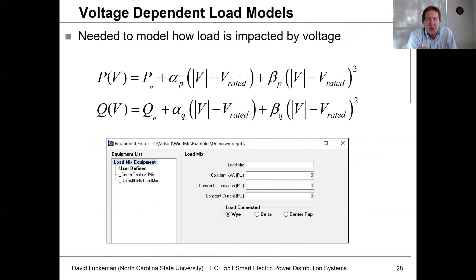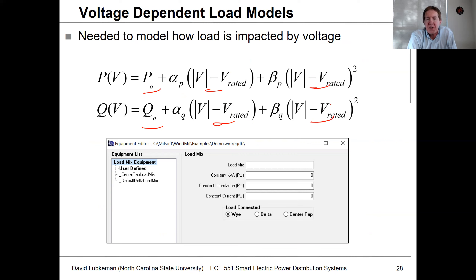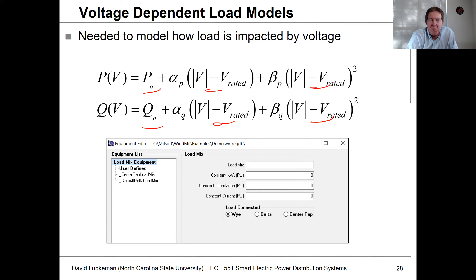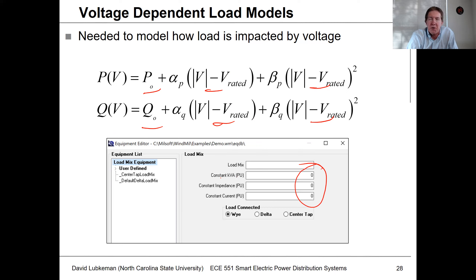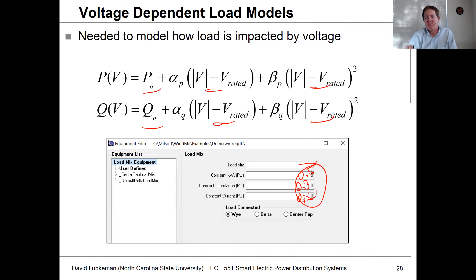Generically, what this looks like: you have the constant power part of the load, and as voltage changes, if you have a constant current component, the real and reactive power adjust by the change in voltage from nominal. If you have a constant impedance part, the change in voltage from nominal squared gives you the impact of voltage on power consumption. In the Milsoft program, if you look at your load mix, you can actually change what this breakdown is — it would normally default to constant power, but you could have something like 0.5, 0.3, and 0.2, which should all add up to one.